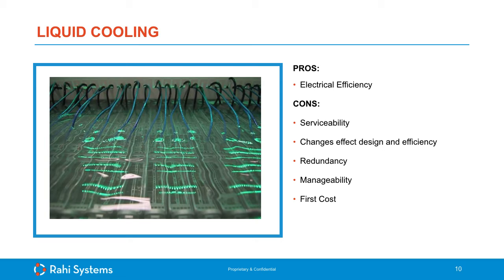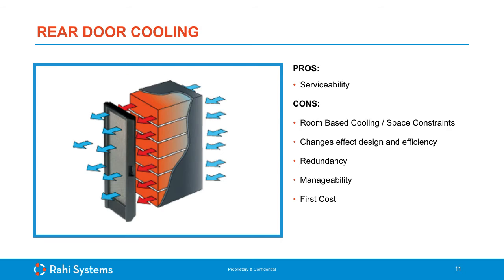So let's also take a look at rear door cooling. Also a close coupled type, close coupled to the rack and to the IT load. Also considered a very efficient cooling approach, and it brings the heat exchanger closer to the IT load. It also eliminates hotspots and can efficiently address much higher densities compared to room-based cooling. Also, of course, much easier to service.